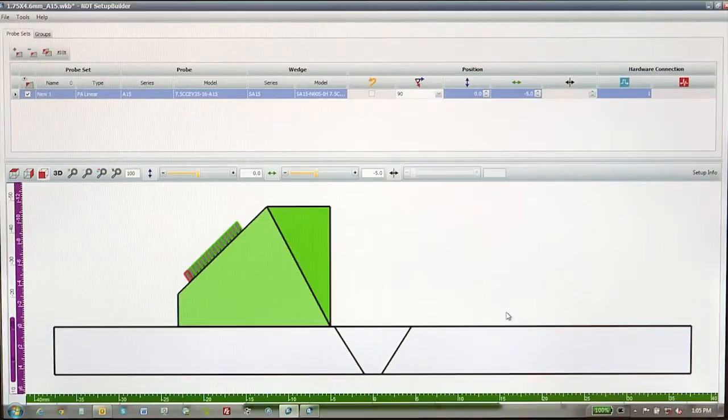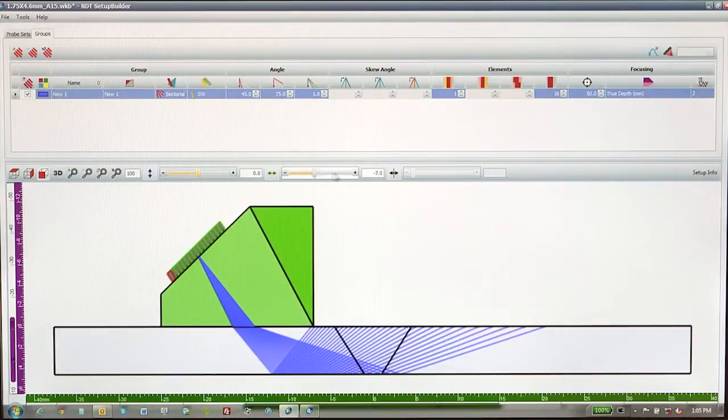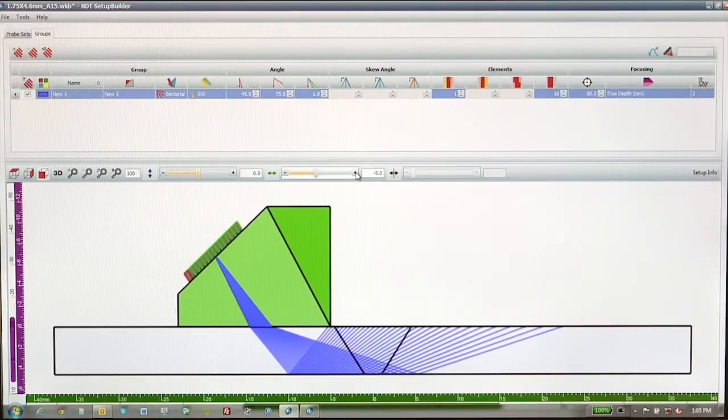The inspection consists of a multi-angle S-scan made of many A-scans that comply with existing codes such as ASME, EN, and similar, for which the beam size, beam angle, and beam focus are programmable by the user.